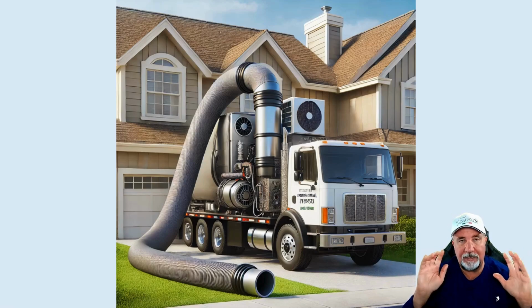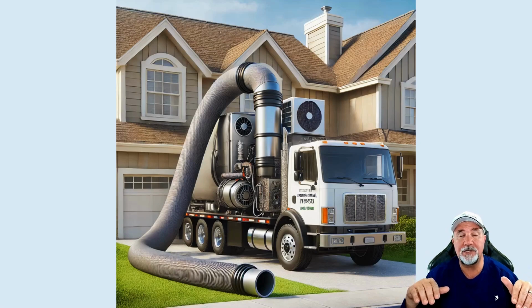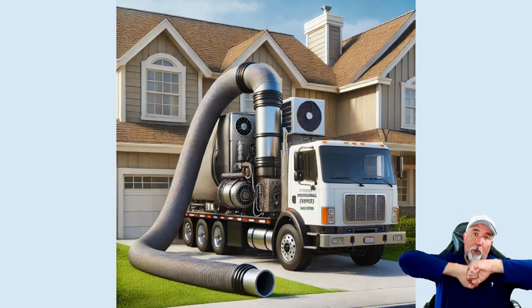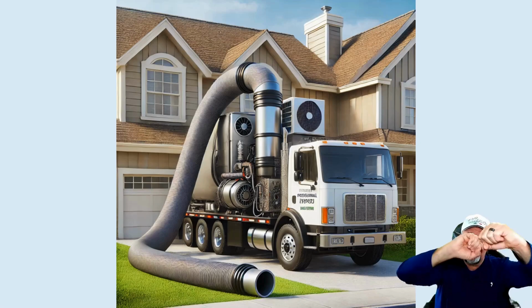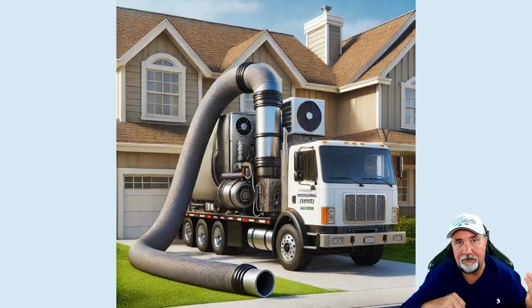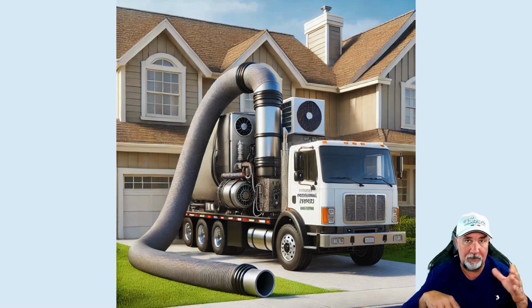You can get away with it sometimes, but I've heard and seen a lot of horror stories where people use the wrong cleaning method and end up ripping the duct system. Because they're not up in the attic doing it, they're shoving hoses up through the vents, they don't know the duct broke because of the process they're using. We'll talk about that in a second.